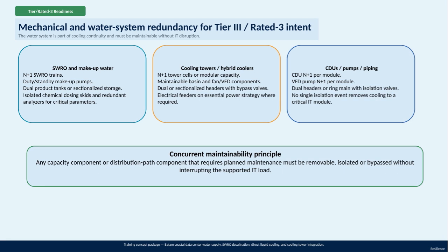For the SWRO and makeup water systems, we implement N+1 redundancy on the SWRO trains, with duty and standby makeup pumps. The system uses dual product tanks or sectionalized storage to ensure continuity. Critical chemical dosing is handled with isolated skids and redundant analyzers monitoring key parameters, minimizing risks from failures. Moving on to cooling towers and hybrid coolers, they operate with N+1 tower cells or modular capacity, and all basin and fan components are designed to be maintainable. The system utilizes dual or sectionalized headers with bypass valves, incorporating electrical feeders managed under an essential power strategy when necessary to further enhance reliability.